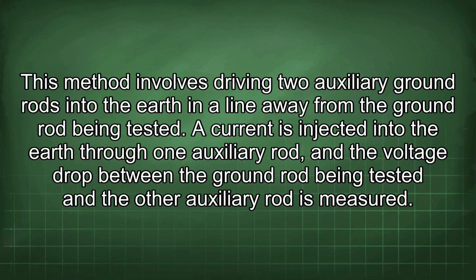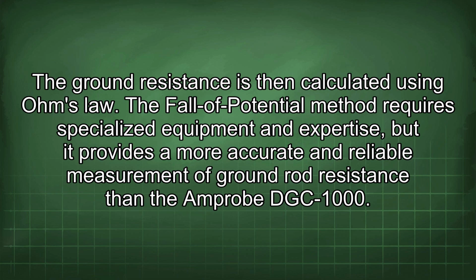This method involves driving two auxiliary ground rods into the earth in a line away from the ground rod being tested. A current is injected into the earth through one auxiliary rod, and the voltage drop between the ground rod being tested and the other auxiliary rod is measured. The ground resistance is then calculated using Ohm's law. The fall-of-potential method requires specialized equipment and expertise, but it provides a more accurate and reliable measurement of ground rod resistance than the Amprobe DGC-1000.